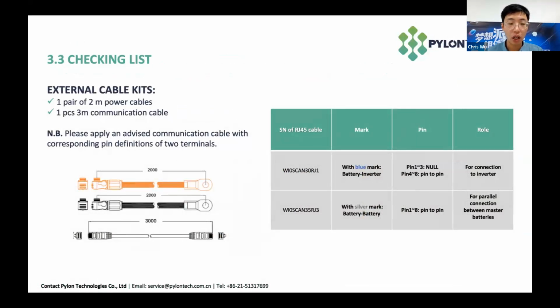In the battery packs, we provide a short power cable and a short communication cable to parallel the batteries. The customer needs to purchase external cable kits to use with the inverter. In the external cable kits, the customer gets two long power cables, 2 meters each as shown here, one for positive and one for negative. He will also get two RJ45 communication cables: one has a blue mark and is used to connect to the inverter, and the other has a silver mark and is used to connect between the master batteries when the customer uses more than one battery group.